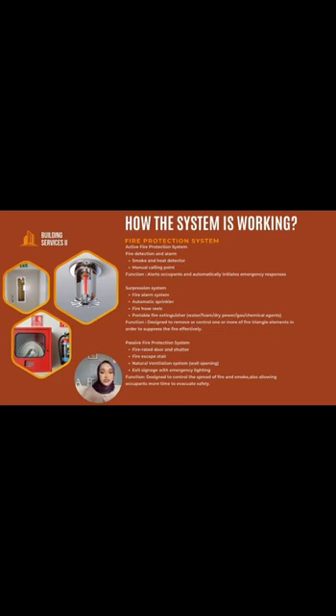Next, passive fire protection systems are designed to control the spread of fire and smoke without requiring activation. As the data collected from the site visit shows, a fire-rated door and shutter function to restrict the spread of fire between building zones. Additional fire escape stairs with ventilation components like wall openings serve to protect the escape route, ensuring a safe route during emergency and allowing smoke and toxic gases to be expelled from the building. Exit signage and emergency lighting guide occupants toward the designated escape route and maintain visibility even during power failure.